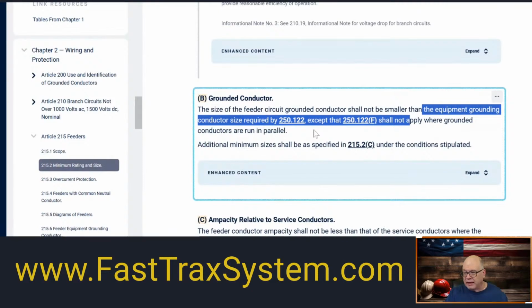that circuit is. Now, the one confusion that people have with this is you're still not sizing the grounded conductor based on 250.122. It just says that it can't be smaller than what the equipment grounded conductor would be required per 250.122. You still got the rules in 220.61 you got to follow. You still have the rules in 250.24 that you got to follow that ultimately are going to send you to 250.102(C). You still got rules you have to follow.